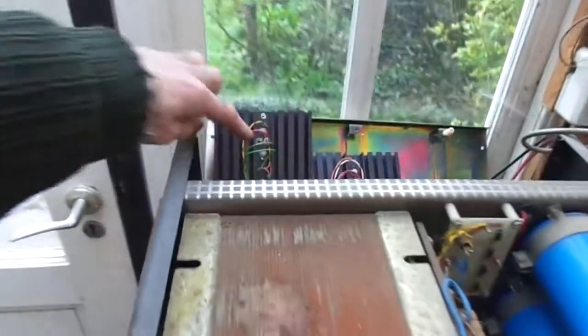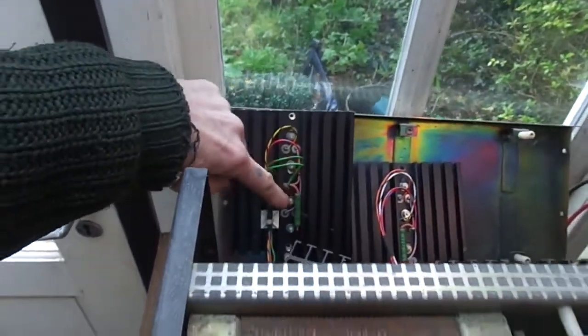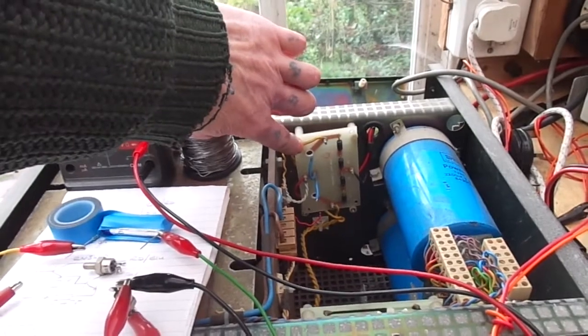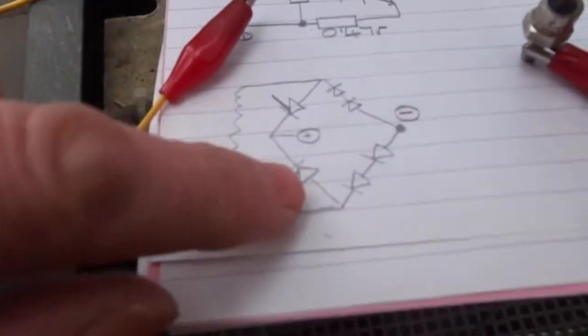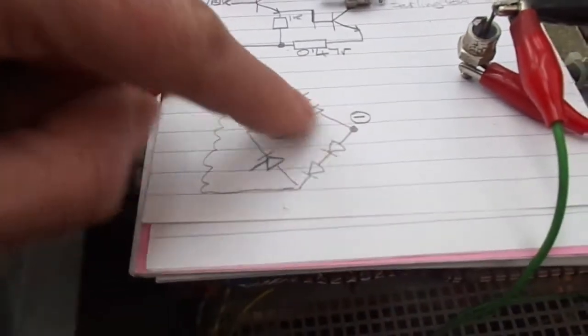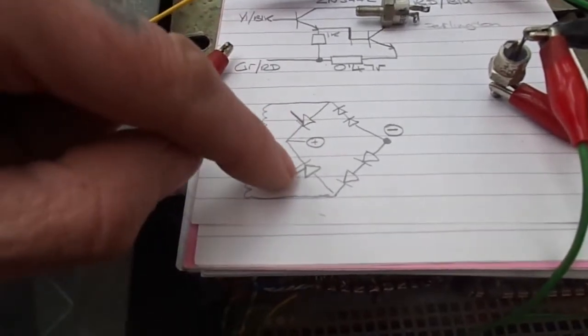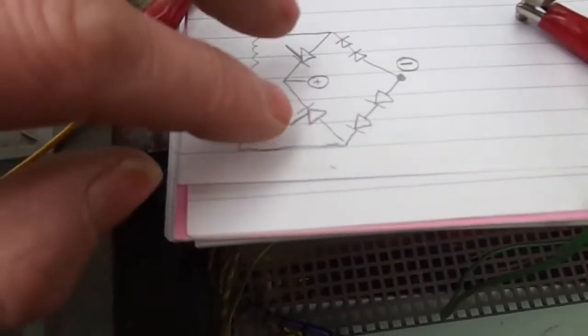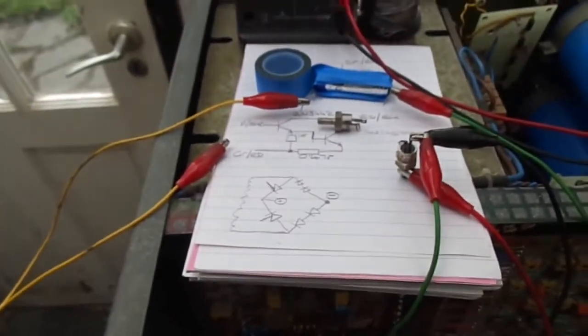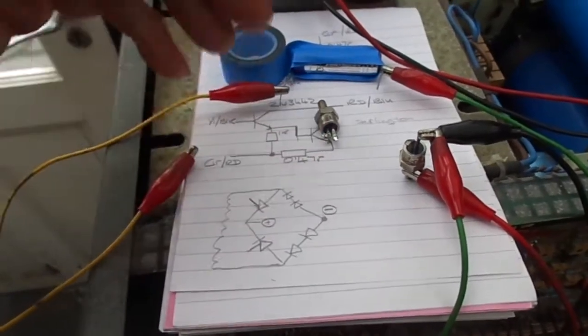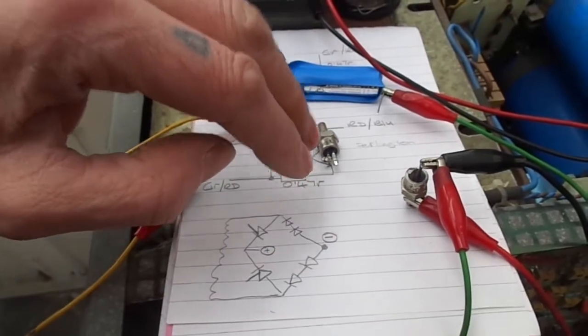So I've started out by just tracing out how these are configured. I thought I'd found a fault. You know, I mentioned those thyristors earlier on. This is how they are wired. This squiggly line here is our transformer secondary winding. These diodes are wired in series to give us our negative voltage. These two thyristors are wired like that. So obviously when we turn the gate on, that's going to allow so much current to flow to the positive terminal. When I checked from cathode to gate, there was basically a short circuit. On the ohms reading, it reads 28 ohms.